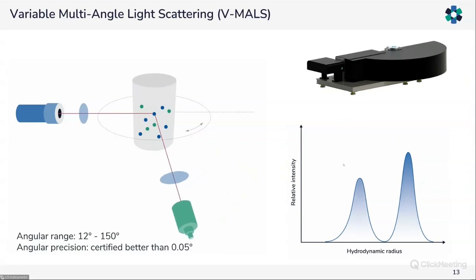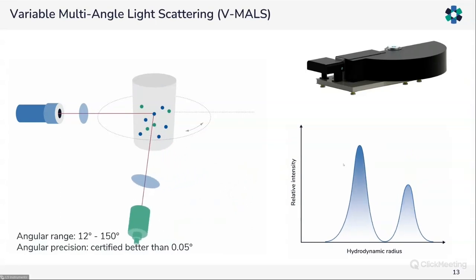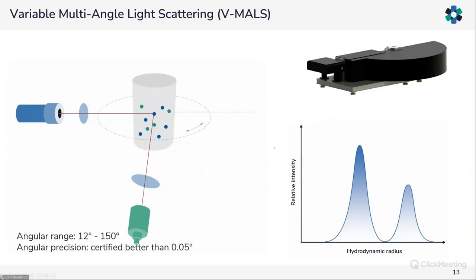The V-MALS capability enables us to vary the angle of the detection unit between 12 and 150 degrees. This is important for poorly dispersed systems because in light scattering, larger particles tend to scatter more light towards smaller angles and will be more visible there. When we want to characterize larger aggregates, we place the goniometer at a low angle for increased sensitivity. Moving to larger angles allows us to better resolve smaller particles. One can therefore improve the sensitivity of the instrument by varying the angle.